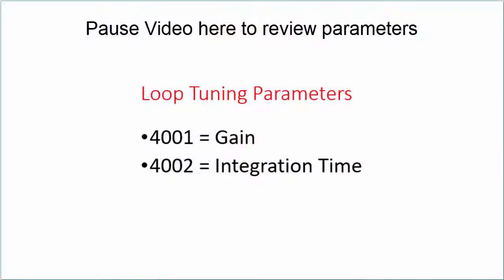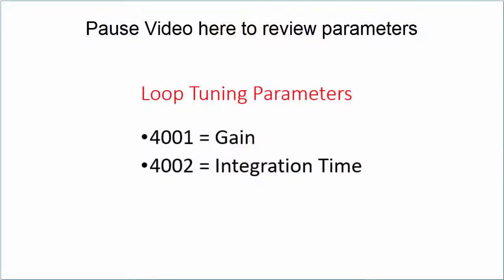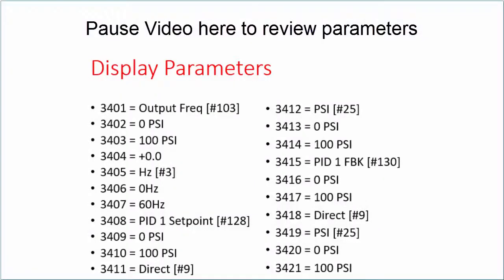These parameters are responsible for configuring the drive's control location and assigning the speed reference function to the internal PI controller. These parameters are responsible for tuning the PI loop itself and will dictate how quickly the drive will accelerate and how responsive to changes the drive's output will be. These values are entered in a trial and error fashion and may need to be repeatedly adjusted to achieve the desired response from the drive's PI controller.